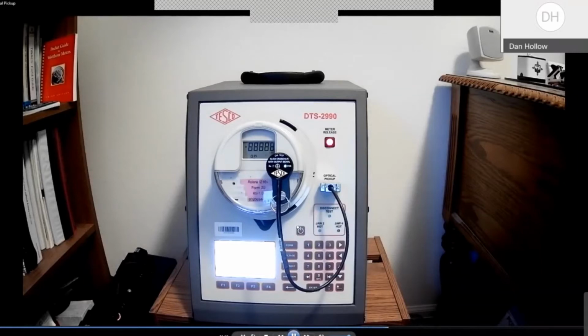So we're going to go ahead and turn on the current to this meter, as I said, at 50 amps. And you'll notice the rapid pulsing of the LED on the left. That red LED indicates every time this pickup is seeing an infrared pulse from the meter relative to the load that it's seeing. So this is 1/4 of full scale for a class 200 meter. So you're getting very rapid pulses on there. This is a one-way pulse. It's just coming out from the meter and being counted by the software in the test board.